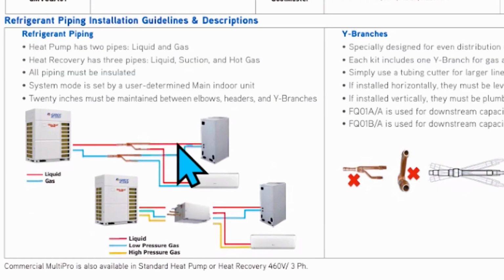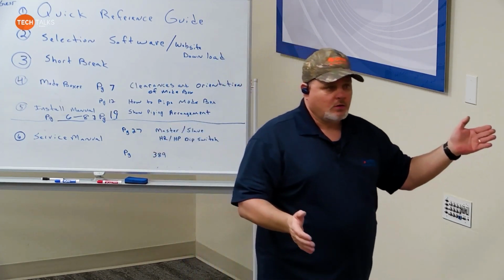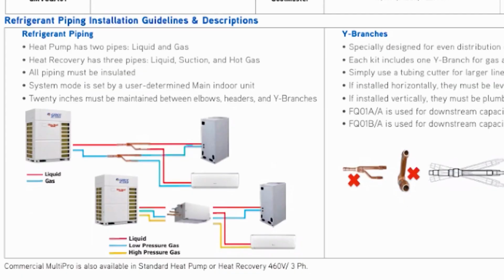But we also need to be careful on the smaller BTU units, like a 9K or 12K: you cannot exceed 50 feet from a Y branch to the indoor unit without a pipe size change. So if you only allow yourself 50 feet, then go pipe it using the size the selection software told you, but actually run 75 feet of pipe, you just made a mistake, because you broke the rule. Sometimes you've got to know those dimensions ahead of time, so just be careful.